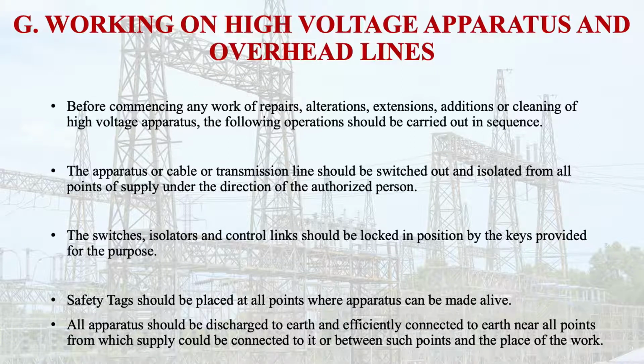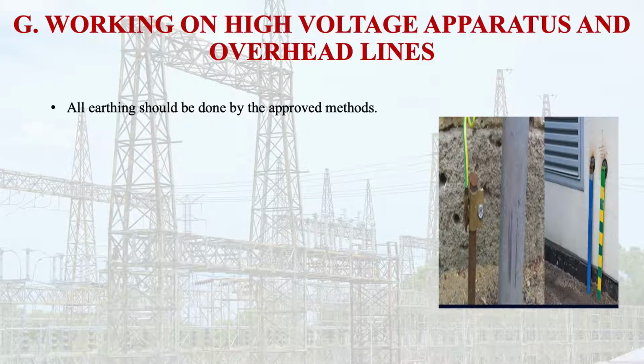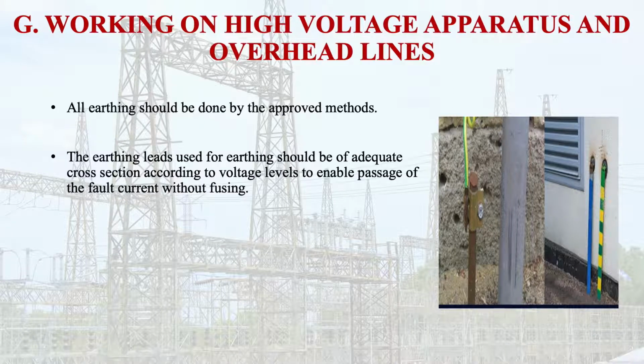So all the apparatus should be discharged to earth and efficiently connected to earth near all points from which supply could be connected to it, or between such points and the place of the work. All earthing should be done by the approved method. The earthing leads used for earthing should be of adequate cross section. It should have the adequate cross section according to the voltage level to enable passage of fault current without fusing.